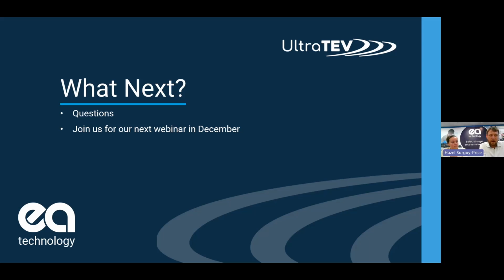LV is slightly different. At LV, insulation is normally to a level where you don't get PD activity, but you still get cable faults, so the equipment I've talked about today isn't the right equipment for that. If you look at our other products on the website, there's a product called VisNet, which is a network visibility tool for LV. That uses something called pre-fault, a similar concept—seeing the pre-arcing to failure—and that works on LV cables, using impedance to fault to see that pre-fault activity. So yes, you can do it on LV, but it's a slightly different failure mode, not strictly PD, and it'd be a different tool set to do so.